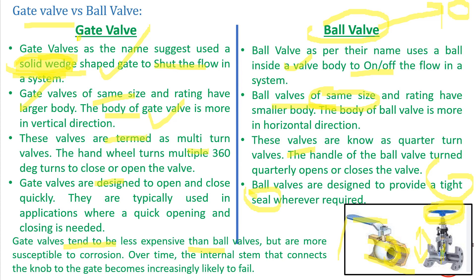Gate valves tend to be less expensive than ball valves because the ball material is costly. Ball valves, due to their compactness, have higher pressure ratings compared to gate valves. Gate valves are more susceptible to corrosion because they have a large amount of solid parts directly exposed to flow. There are also maintenance issues — sometimes the wedge gets disconnected from the spindle, and in that case the complete gate valve needs to be replaced.